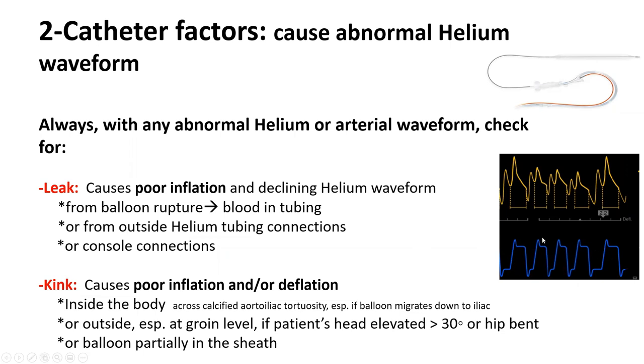And whenever you have distortion of both, or just distortion of that helium waveform, sometimes before you get distortion of the arterial waveform, you should think of those two major catheter factors, leak and kink. A catheter leak can cause poor inflation, because it's leaking, and a decline in that helium waveform. So you start seeing the inflation is less and less with every beat. And what are the causes of leak?